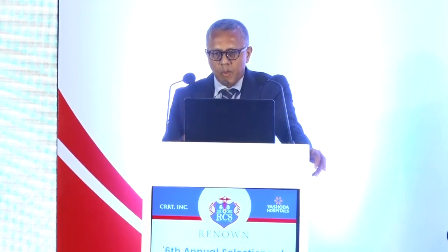Moving to CKRT alarms: this is a schematic of what the circuit looks like. We have the blood component where an access pulls blood from the patient, perfuses through the filter, and returns to the patient in a veno-venous access. We have a dialysate port running and replacement fluid which can be run pre-filter or post-filter. The anticoagulant is generally run before the blood pump and the pre-filter fluid. Most CKRT machines monitor at least four pressures. The first is the access pressure, a pre-pump pressure that tells us about the integrity of the vascular access and the blood flow rate being generated.